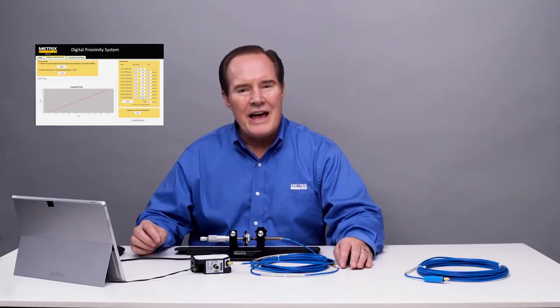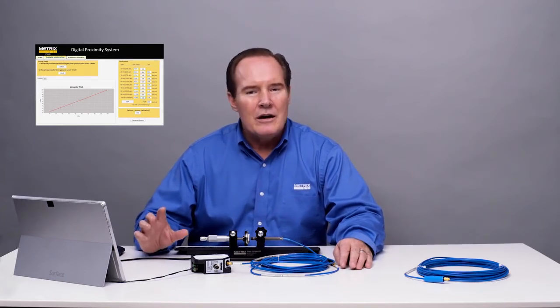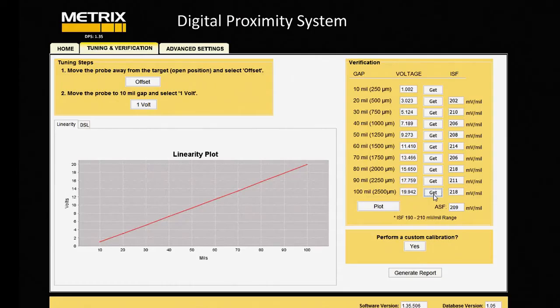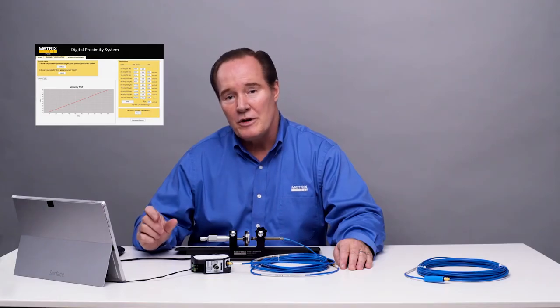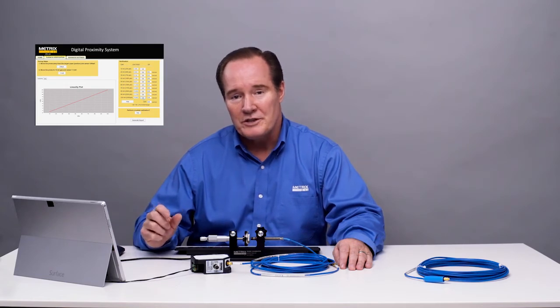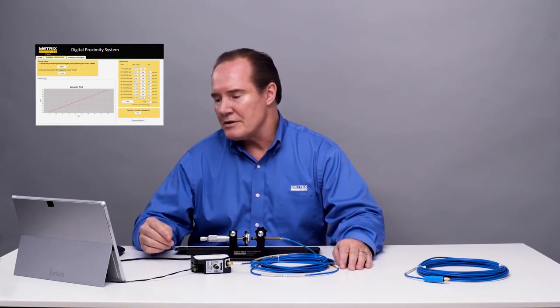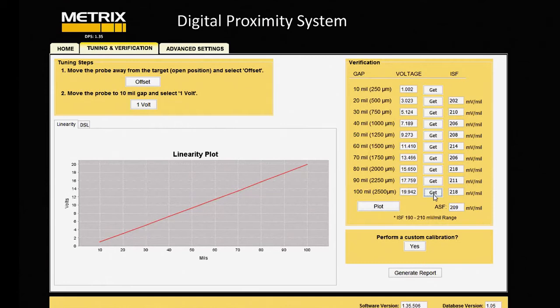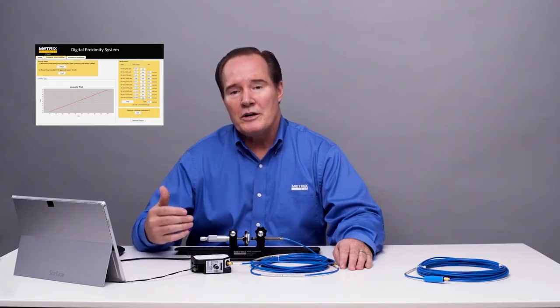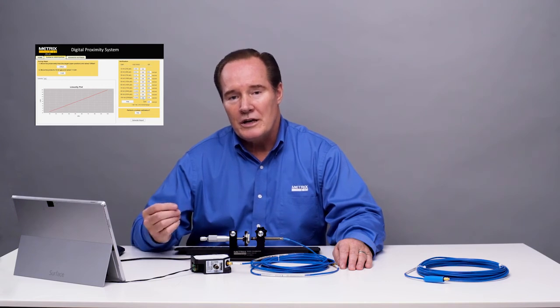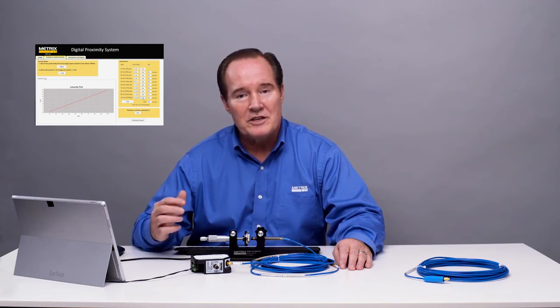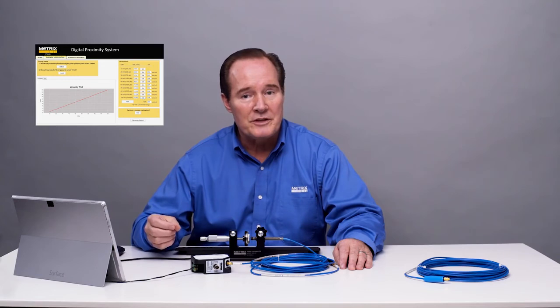All right, we gathered our last point, and you can see that many of the points are in specification, but we have about a third that are out of specification. They're beyond the 190 to 210, which is the allowable range. So we have some as high as 218. Well, that's not really that bad since we just cut the cable and put on a connector. So what we want to do is go in and do a custom calibration and then see if we can tighten this up to make sure it's within specification.